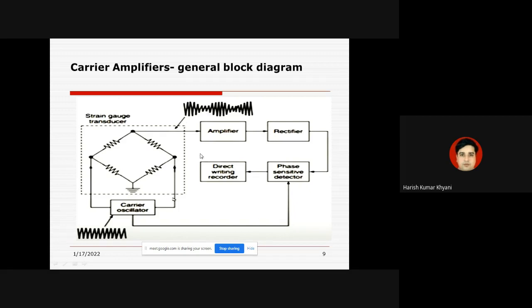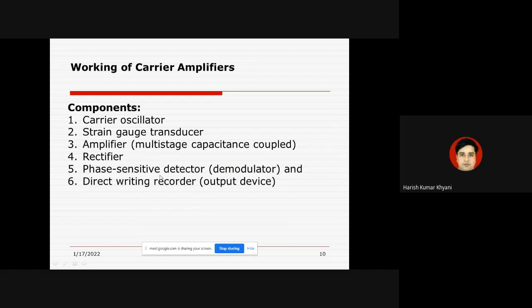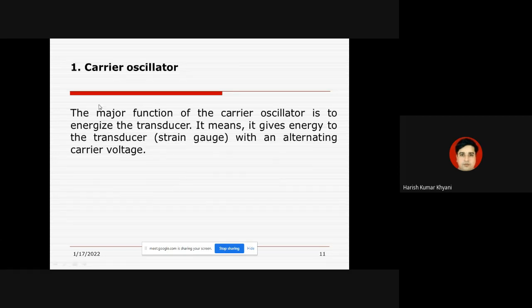There are six components in the general block diagram of a carrier amplifier: number one is the carrier oscillator; number two is the strain gauge transducer; number three is the amplifier, which is a special type — a multi-stage capacitance-coupled amplifier; number four is the rectifier; number five is the demodulator, that is the phase sensitive detector; and number six is the direct writing recorder, which is the output device.